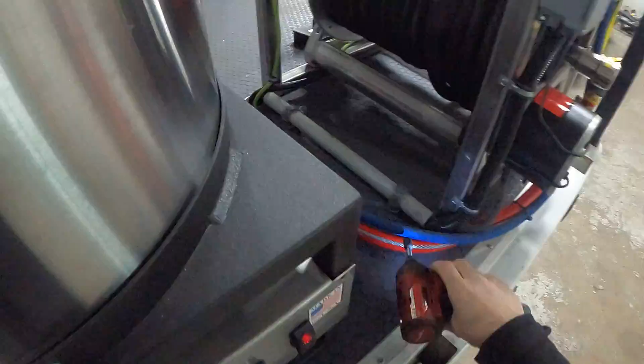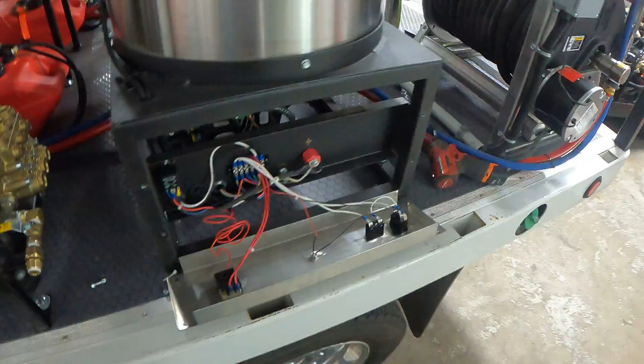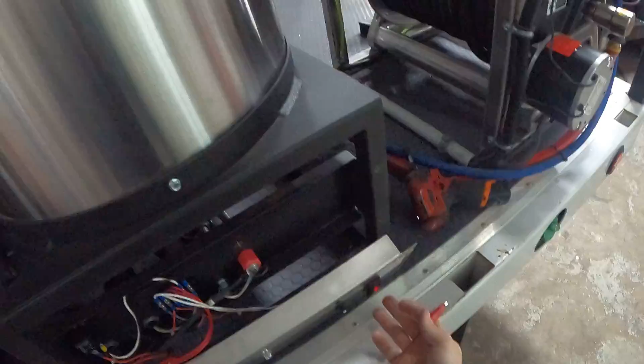I'm gonna shut this off right now. There is a manual circuit breaker here, and there is also a circuit breaker which is labeled in your wiring over there. So you see over here, I'm gonna turn this on for you. This will not actually activate until you have pressure here, and this pressure switch senses pressure. So if you leave this on, be very careful, because you can have this on at any time. So make sure you leave this off. If this is powered on, this relay will draw a very, very minimal amount of current, but it will still be drawing current. So be aware that that is an issue if you forget and leave that on.